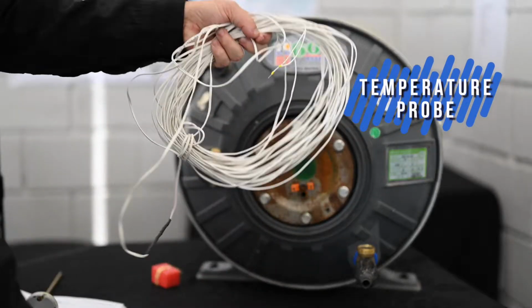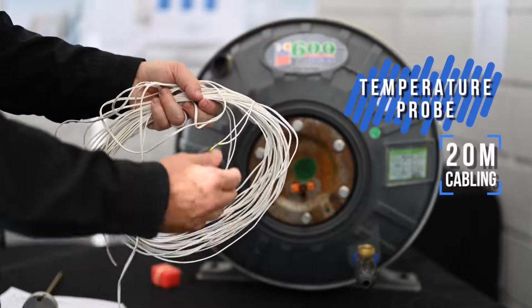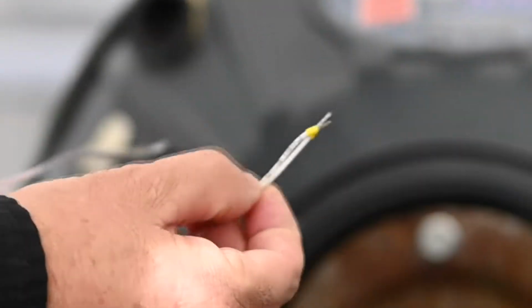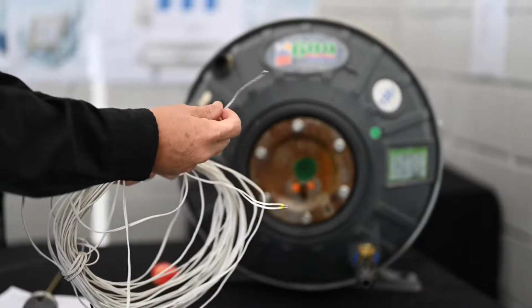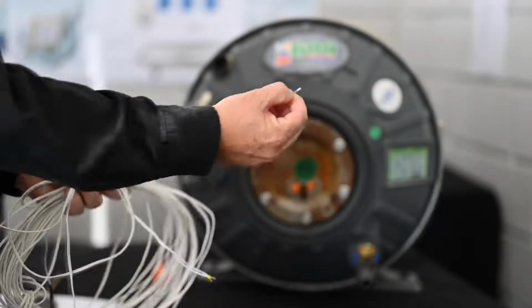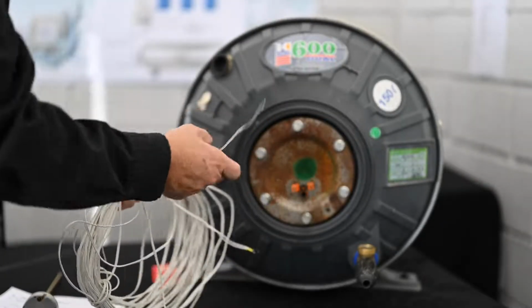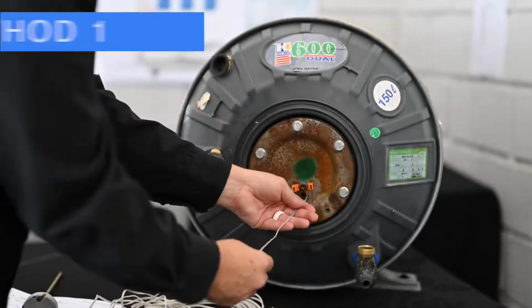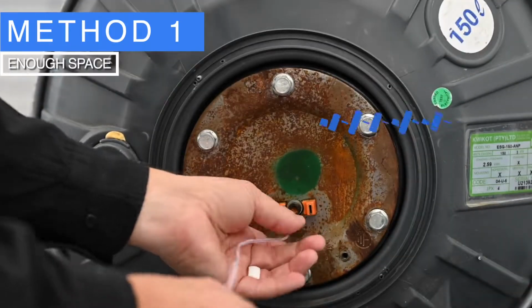Now the reason we're removing it is because we want to insert a temperature probe. Microcare supplies you with a temperature probe and 20 meters of cable. On the one end is where we actually connect into the geyser controller, the other end is this temperature probe. So we actually want the temperature probe in there to read temperature. There's a few ways you can do it. One of them is, if you have space, to simply insert it all the way.